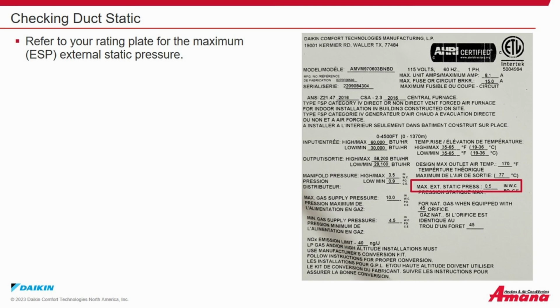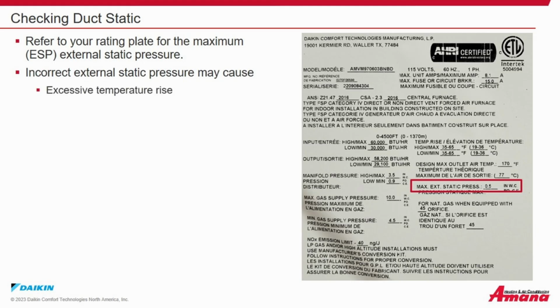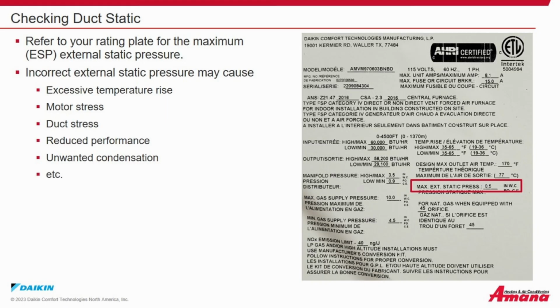Checking duct static. Refer to the unit rating plate for the maximum external static pressure, or ESP. Incorrect external static pressure may cause excessive temperature rise, motor stress, duct stress, reduced performance, unwanted condensation, etc.